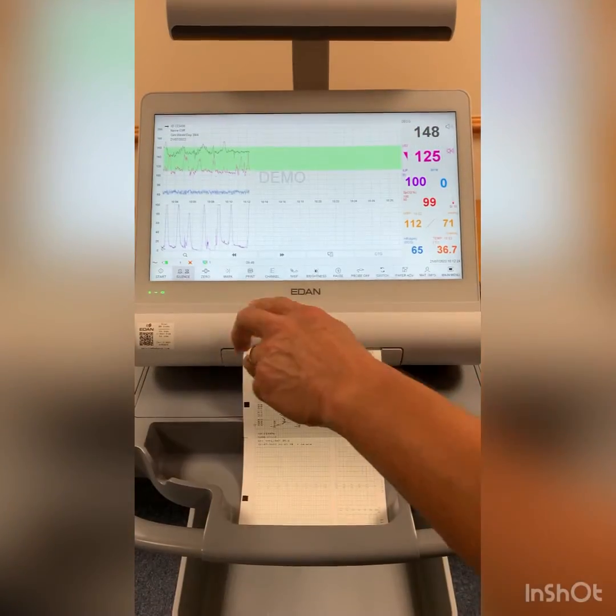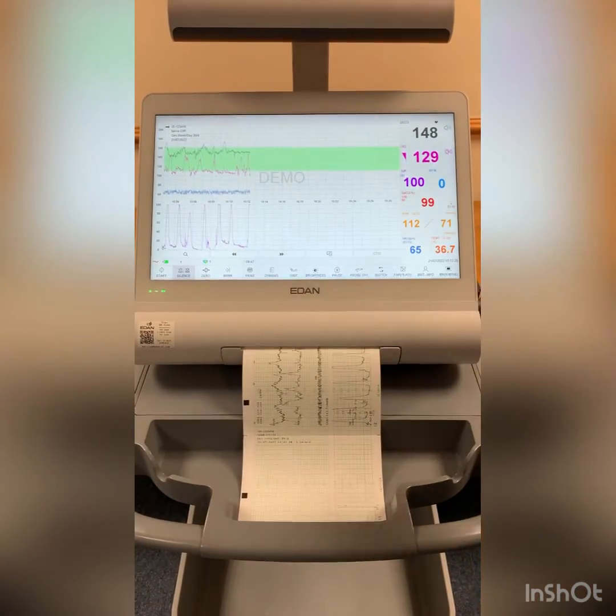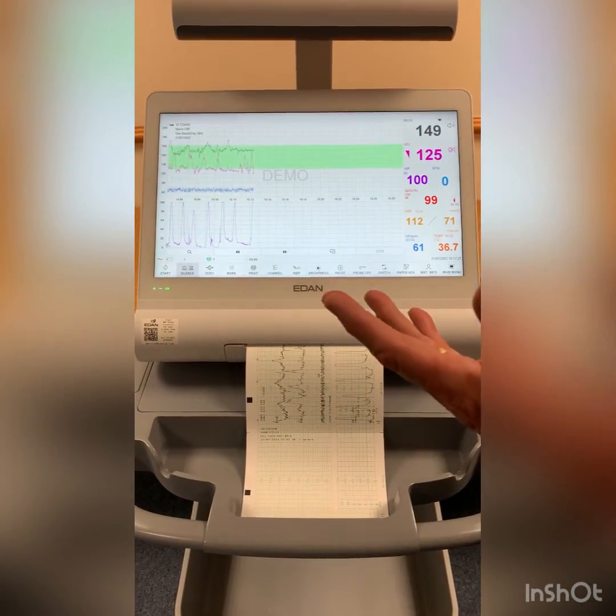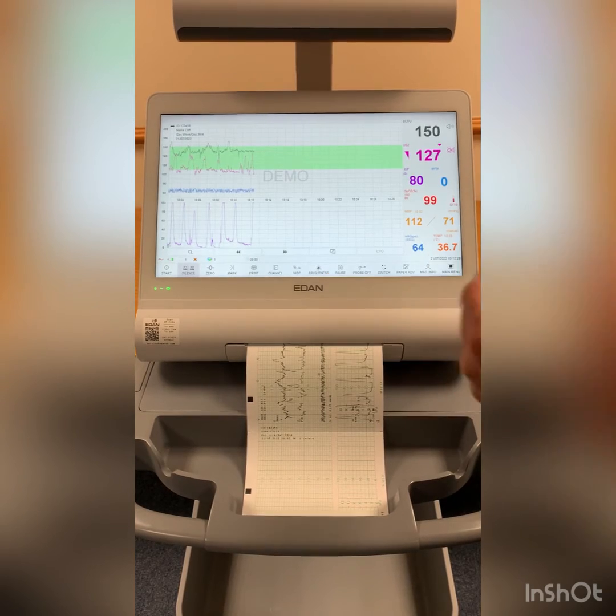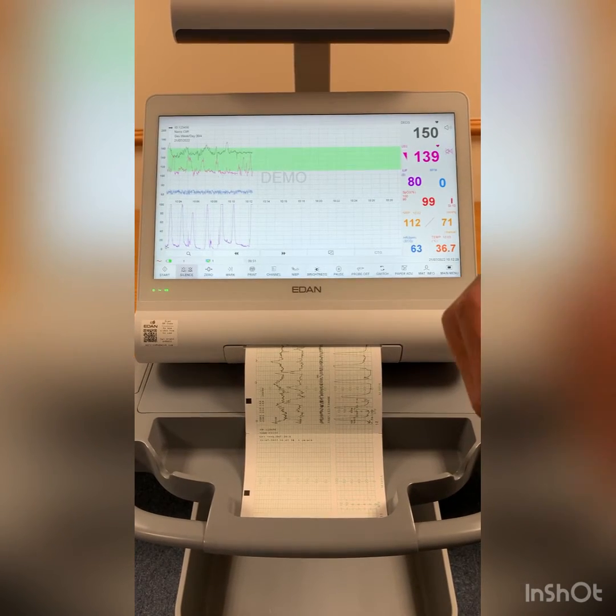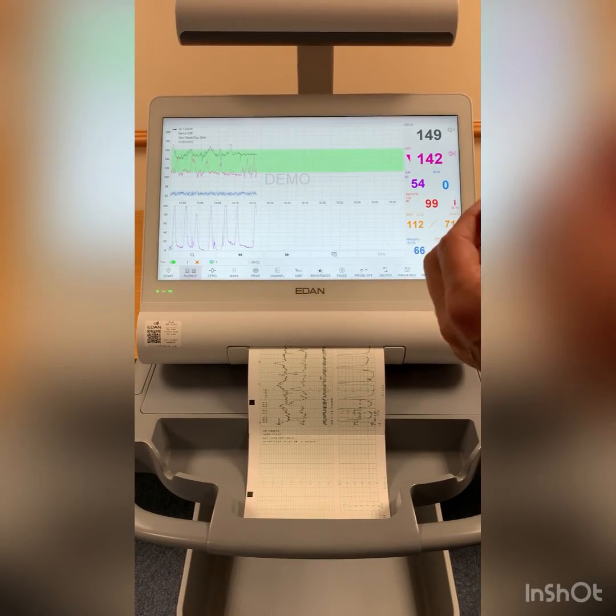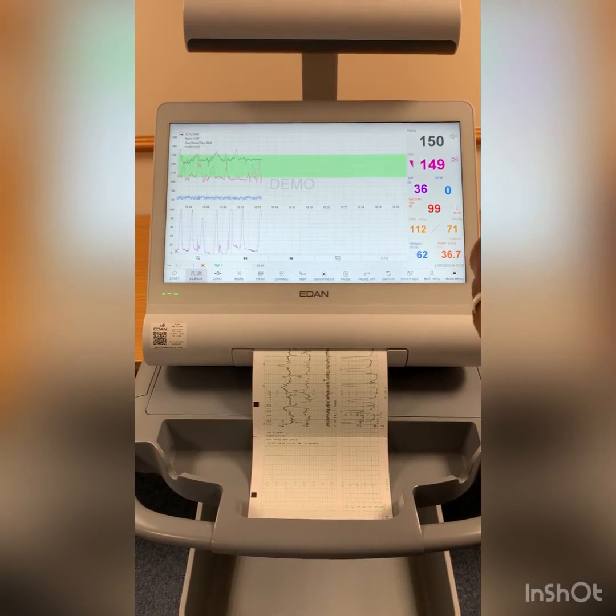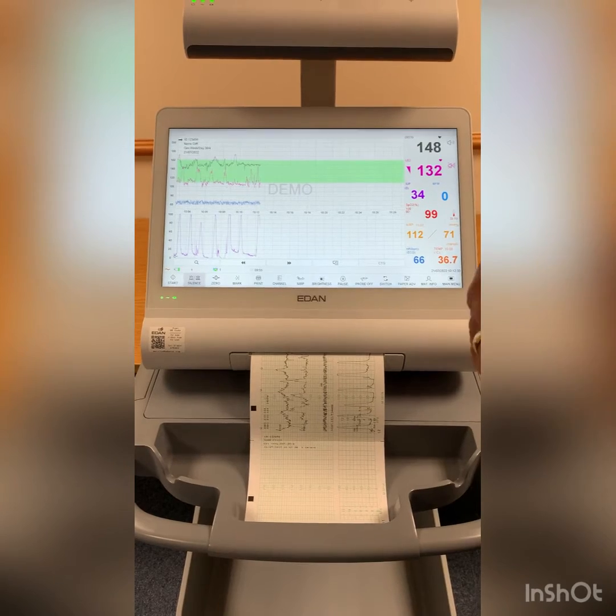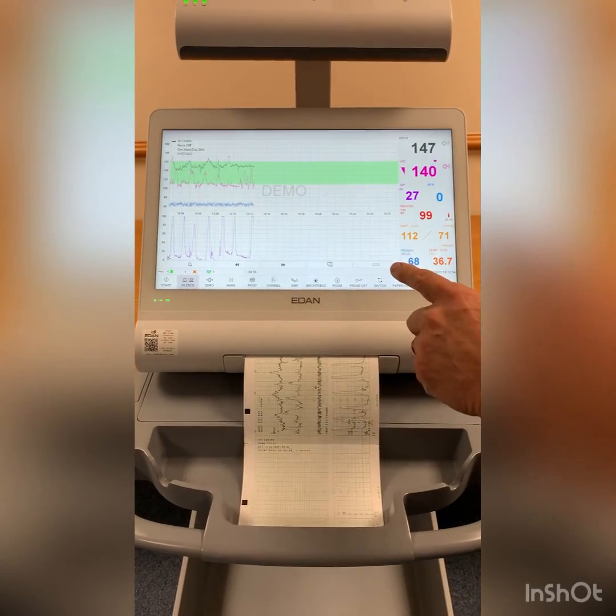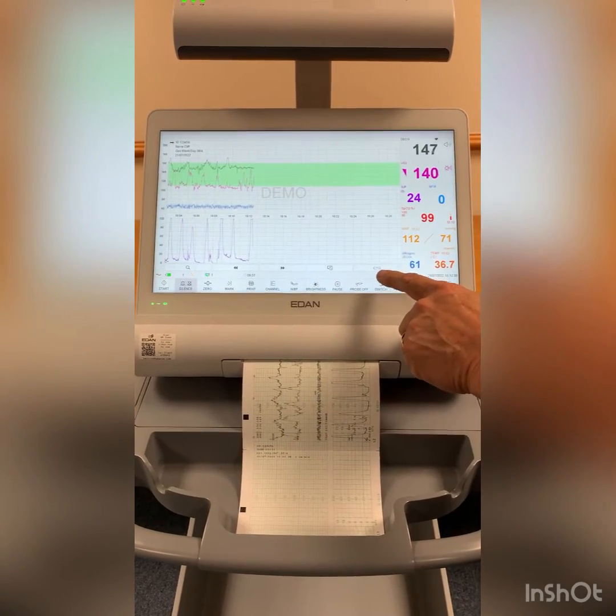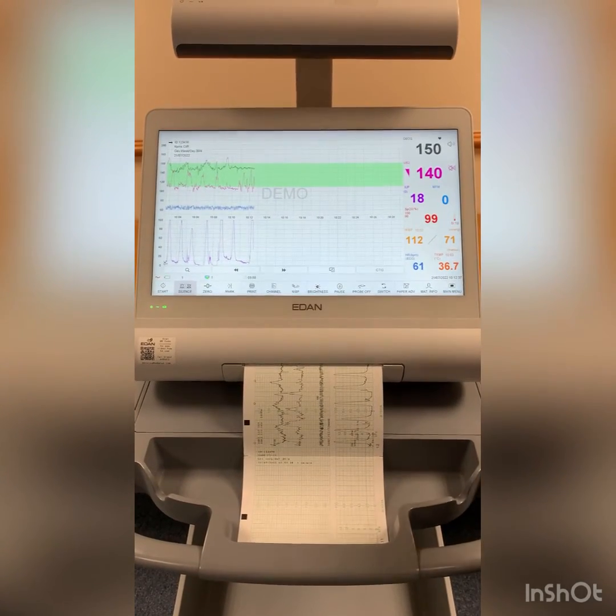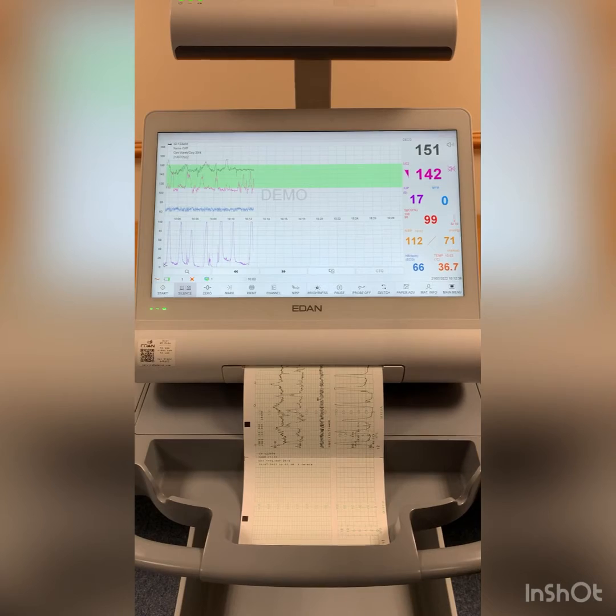If we now look at the screen, we're looking at 9 minutes 47, 48 seconds. While I'm talking about the monitoring — after 10 minutes the system will analyse, and then we should see this CTG button turn green accompanied by a beep.